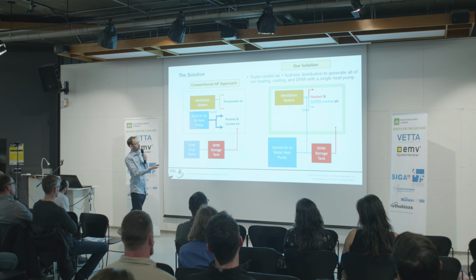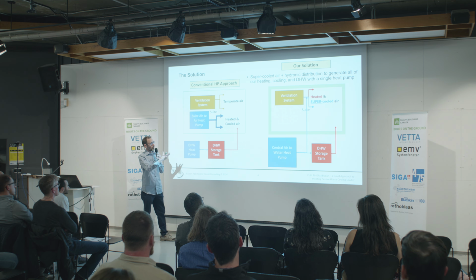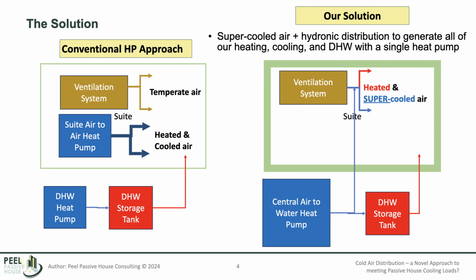So this is our proposed system for this research project: essentially taking our ventilation system and then heating and cooling that air. That's going to be the only mechanism by which we deliver heating and cooling into the building. And if we switch to a hydronic system, an air-to-water heat pump, we can technically have one heat pump do all of the heating, cooling, and hot water. So the goal here is we try to simplify the system and maybe save some costs.